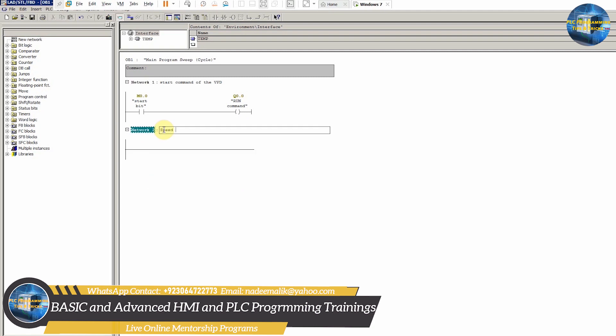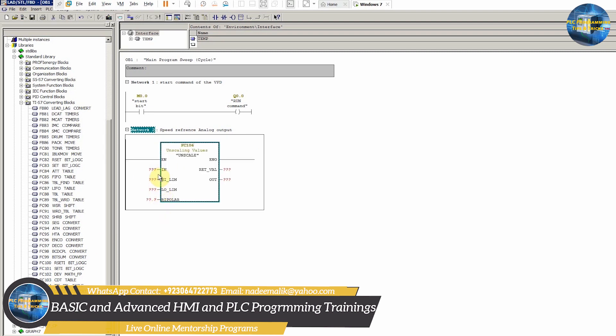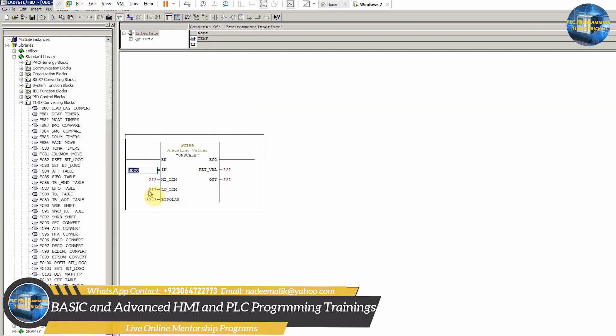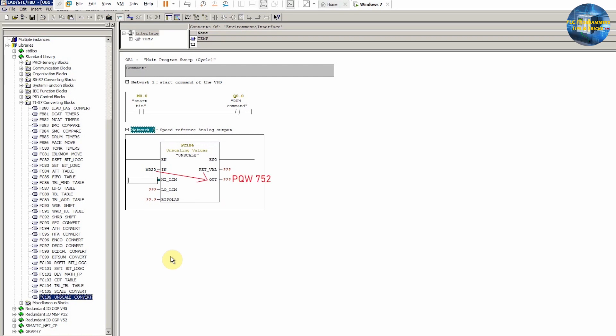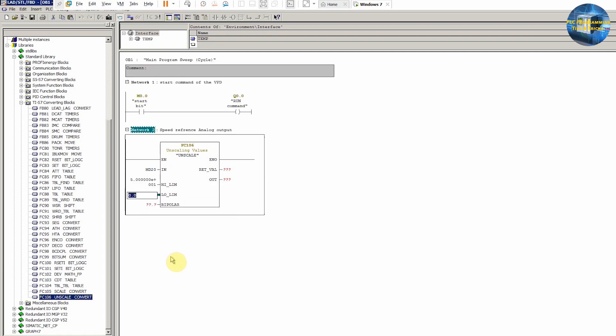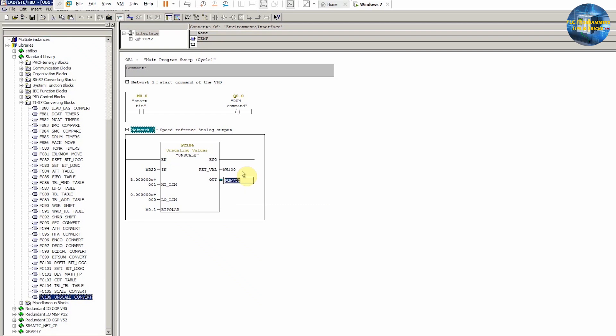Q0.0 will turn on the relay to start the VFD. In network 2 we will make logic to send the speed reference analog signal to the VFD. We will insert the FC106 unscale function on the ladder. We will enter MD20 at the input of this FC106 function — whatever real value we enter in MD20, it will get unscaled and go to the PQW752 analog output data register. We set high and low limits as 50.0 and 0.0, as we want to run the VFD between 0 Hz and 50 Hz. We enter PQW752 at the output of the FC106 function.